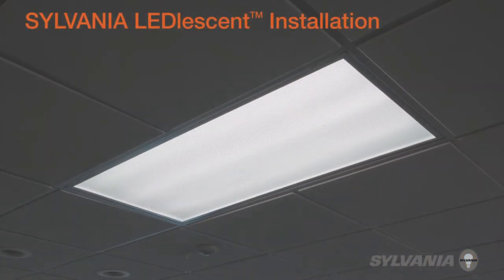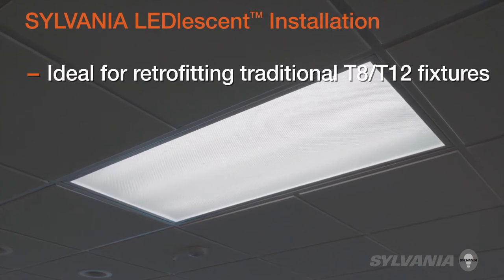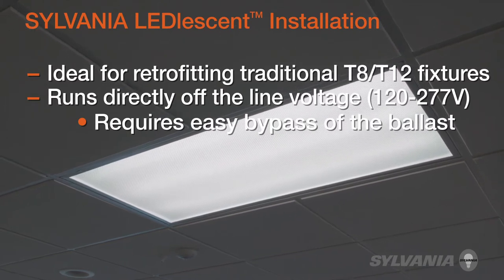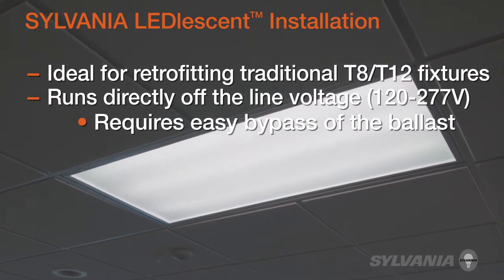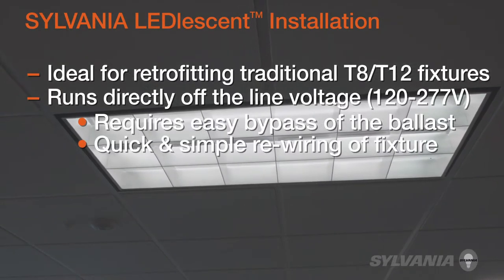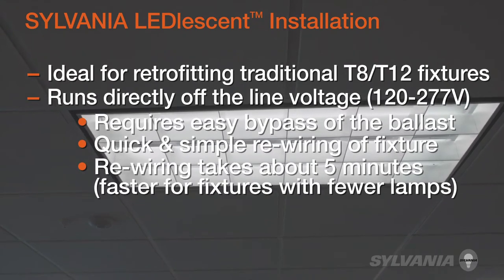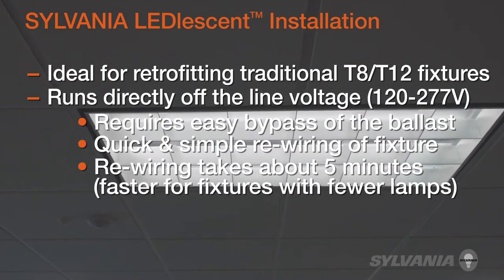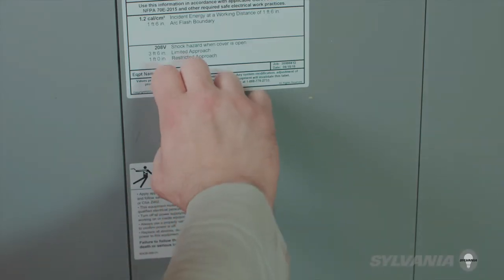Sylvania LEDlescent T8 ballast-free lamps are ideal for retrofitting traditional T8 and T12 fixtures with energy-saving LED lamps. LEDlescent lamps run directly off the line voltage, bypassing the ballast in existing fluorescent fixtures. This requires a quick and simple rewiring of the existing fluorescent fixture, which can be accomplished in place in about 5 minutes or less for a 4-lamp fixture, or even faster if the fixture has fewer lamps.